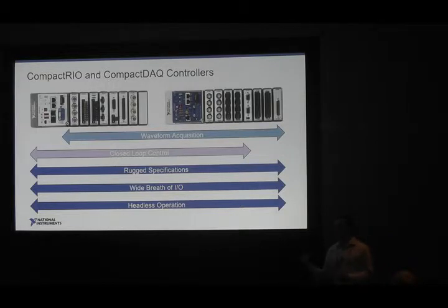And so Compact DAQ controllers today can manage that to a certain point, usually up to about the tens of hertz. So it does actually bleed a little bit into the control space. And then CompactRIO, with the flexibility, there's a lot you can do with it. You can do a lot of measurement stuff and custom measurement stuff, but it's not always the easiest to use as you're trying to do that as well.